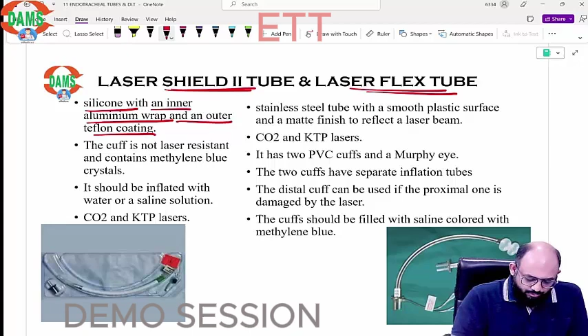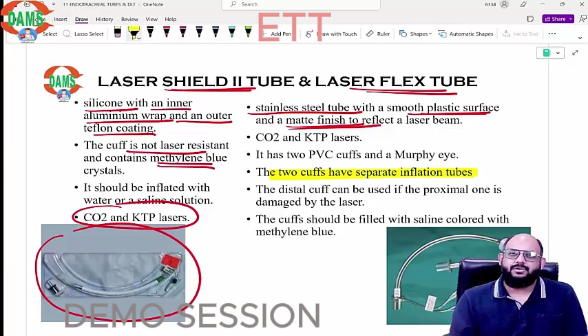Laser-Shield II is silicone with an inner aluminium wrap and outer Teflon coat. So you will see aluminium and Teflon. Its cuff is not laser resistant, it contains methylene blue crystals, so if it bursts, blue will come out. And it is for CO2 and KTP laser. Whereas the Laser-Flex tube has a stainless steel tube with smooth plastic surface and a matte finish to reflect the laser beam. The standout feature of a Laser-Flex tube is two cuffs with two separate inflation balloons, so that in case there is a break of the cuff because of the laser, then you can use another cuff.